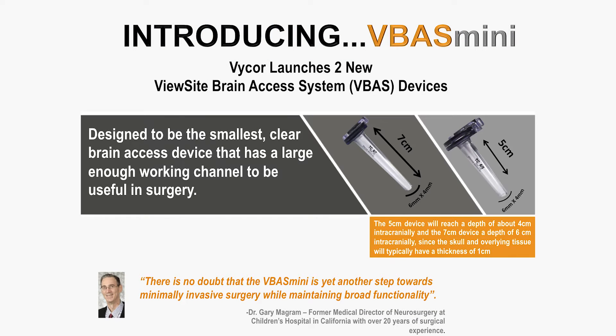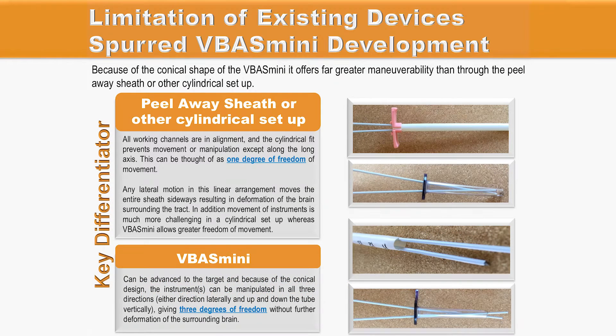The VBASmini is the first and smallest clear brain access device that presents a large enough working channel to be useful in neurosurgery. It can be easily advanced toward the lesion; the transparency of the wall allows constant monitoring of the surrounding structures, and the elliptical shape allows instruments to be manipulated in all three directions — either laterally or up and down — giving a so-called three degrees of freedom.